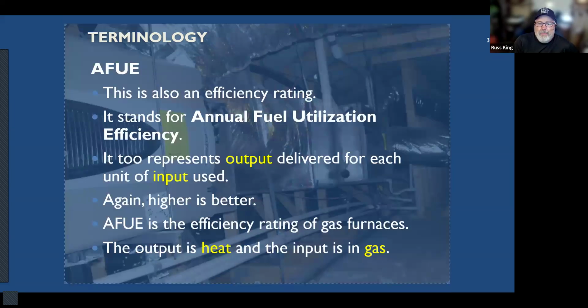Okay. So now let's talk for a second about furnaces. Okay, furnaces are still very common, especially in existing homes. There's a big push now to get rid of furnaces and replace them with heat pumps. Okay, but there's still a lot of furnaces out there, and the efficiency rating that we use for furnaces is actually quite simple. It's called the AFUE, or annual fuel utilization efficiency. All right. And it represents how much heat we're getting out based on how much gas we're putting in.